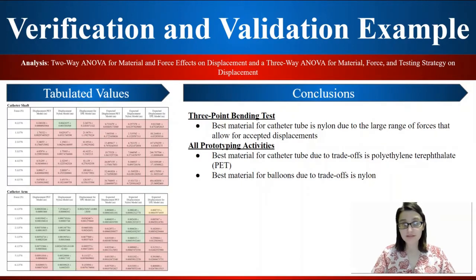Virtual simulations were done. These deflections were then placed into a virtual simulator with applicable standard deviations to run extraneous trials. So the output was then tabulated with green representing those values that fall within the acceptance criteria. With just 3-point bending, nylon was the best material for the catheter tube. It could stay within that acceptance criteria under even the largest of forces. However, with all other prototyping activities, we found that polyethylene terephthalate is actually the best material for the tube, while nylon is the best for the balloons.